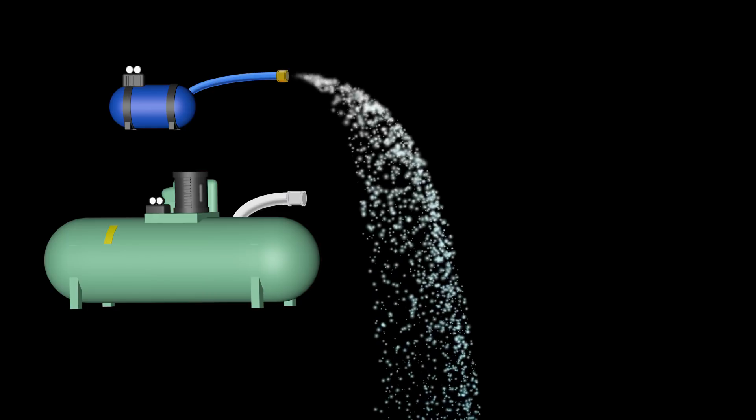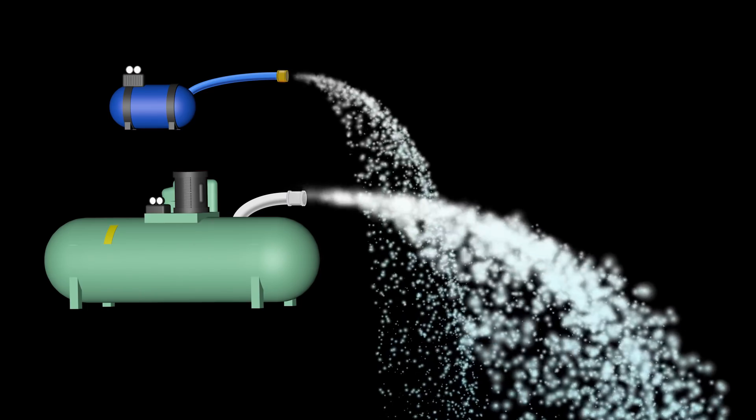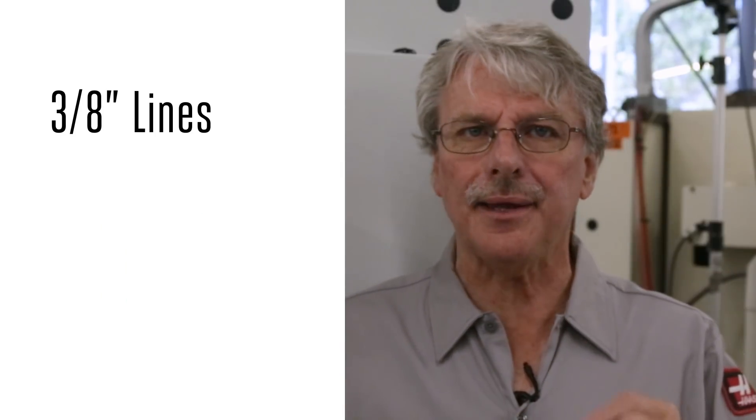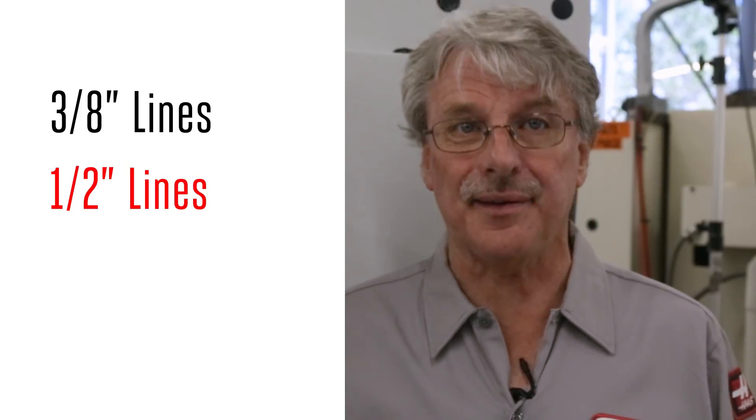First, you need a big enough compressor to match the volume needs of all your machines. But second, you need large enough air lines to deliver that volume to each of them. Just as a compressor tank only holds so much volume, narrow air lines limit the amount of volume that can get through them. So we recommend 3/8 inch lines, but half-inch diameter lines would be a great way to go as these will give you more volume of air to each machine.